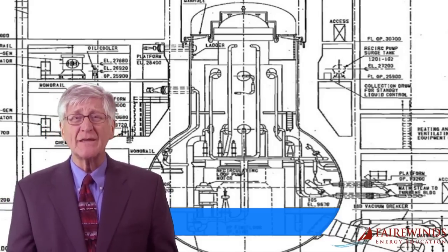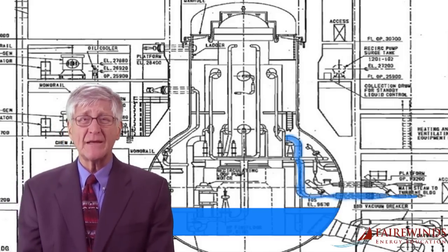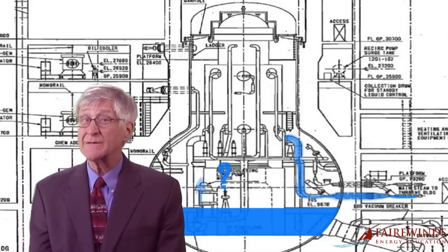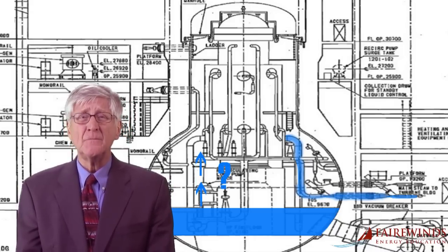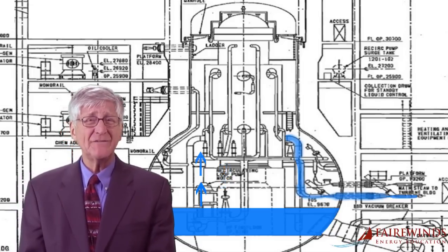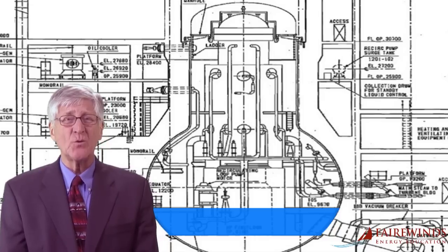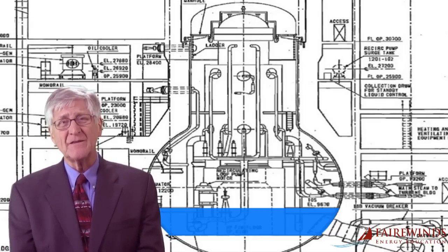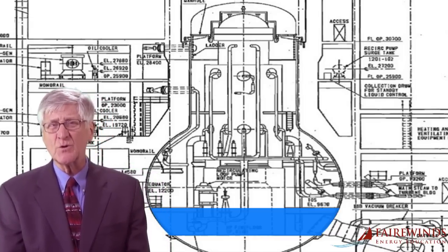This drawing shows that the water level inside the containment is much lower than where TEPCO claims the new leak was found, and we all know that water does not flow uphill. Even more perplexing is the fact that the radioactivity in the leaking water is a hundred times less radioactive than the water normally found in the basement of the containment, but a hundred times more radioactive than the water currently being pumped in to cool the molten remains of the nuclear core.